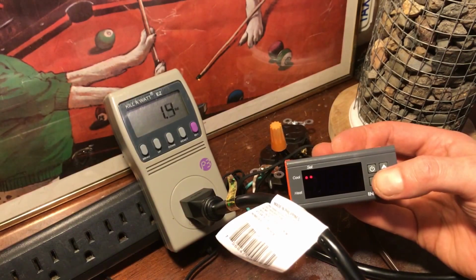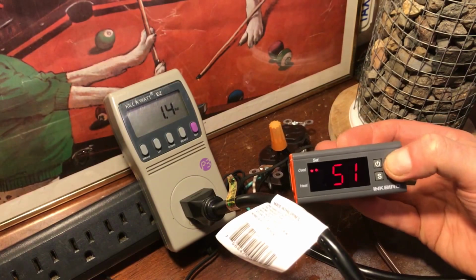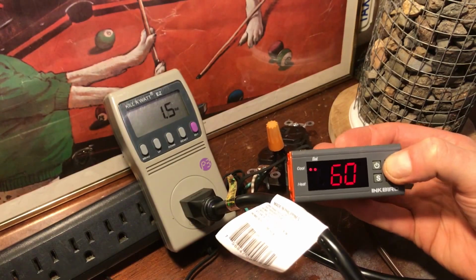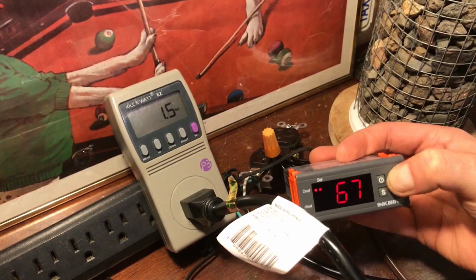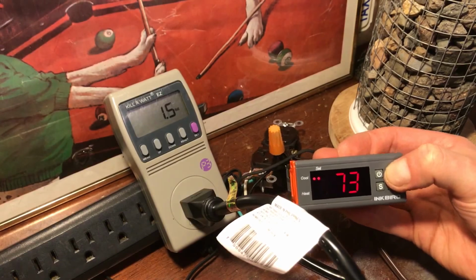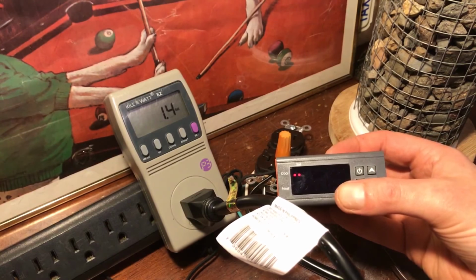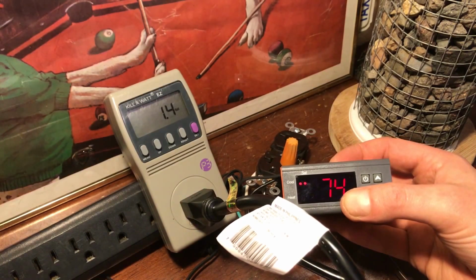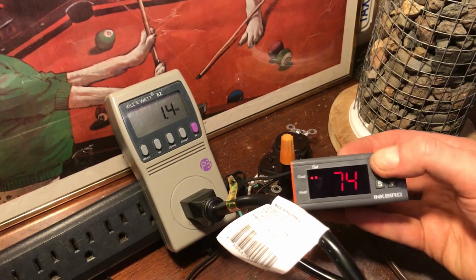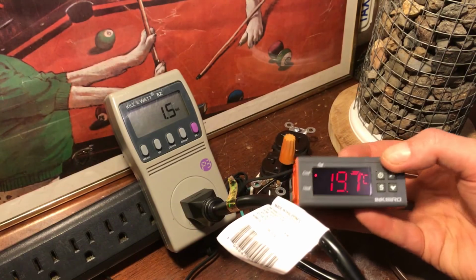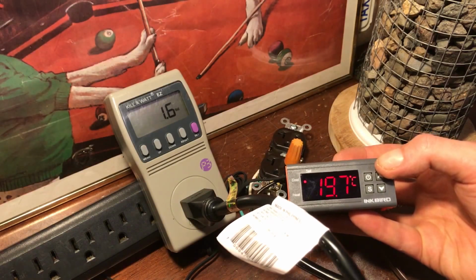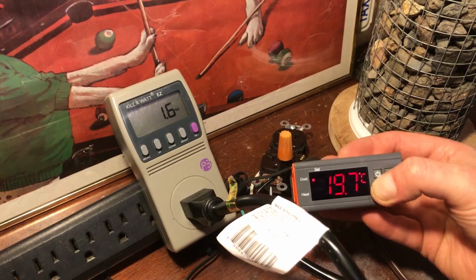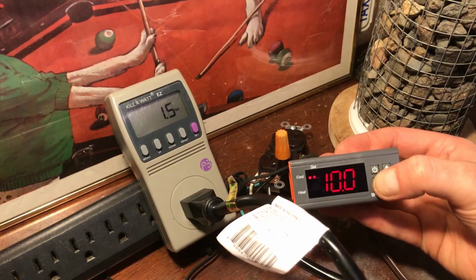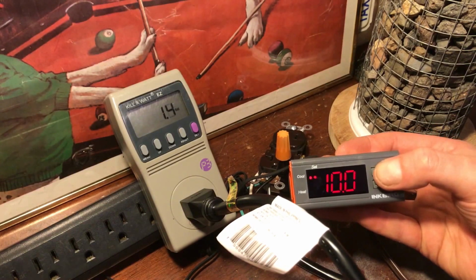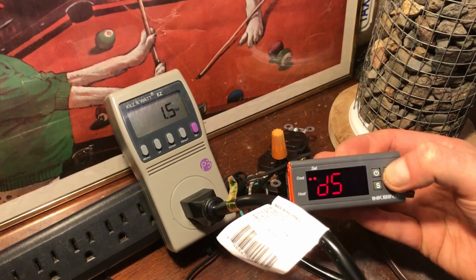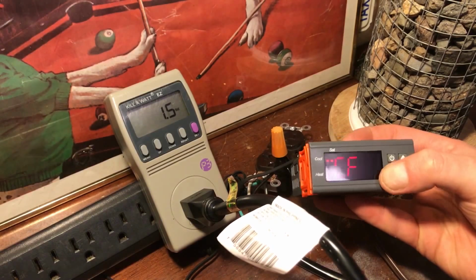Okay, so the set point currently is 50. So let's go ahead and bump this up. I'm going to run it at 74 with a differential of 2 degrees. So in other words, when it hits 72, it'll stop heating, it'll turn off the heater. And then when it hits 76, if it does, it'll turn on the exhaust fan as my cooling unit. Okay, so let's go back to that. Okay, so that's the set. Oh, see, it didn't save any of that because we didn't hit the on-off button. That is annoying.